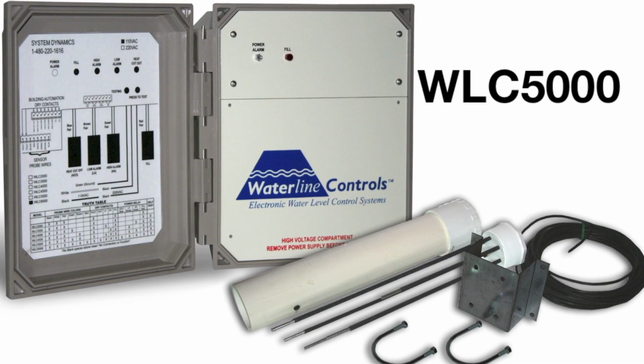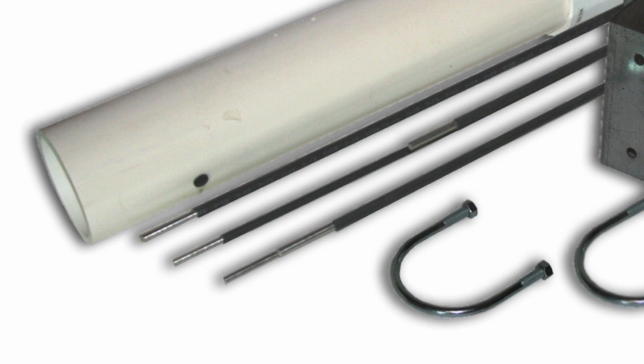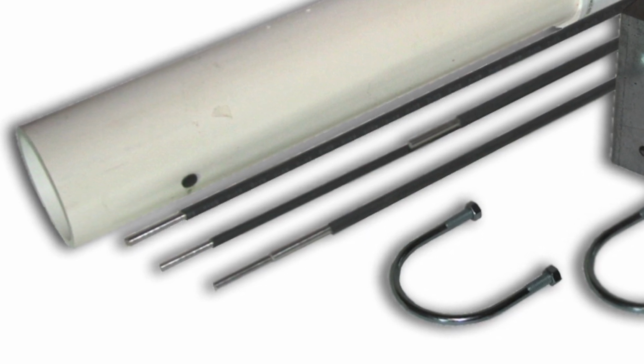The WLC 5000 is an ideal solution. The pins are stainless steel rods mounted into a housing, and that housing is mounted in the wet environment or externally on the side of the cooling tower, depending on how you want to do it. They're threaded on the end, so they can be extended to any length you want. They're jacketed and color coded, and the color codes match the wire codes on the panel, making it very easy to put together.